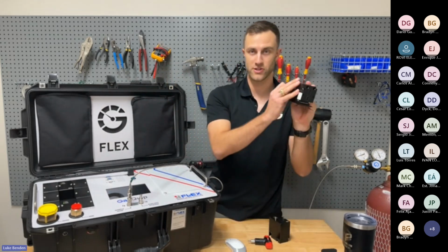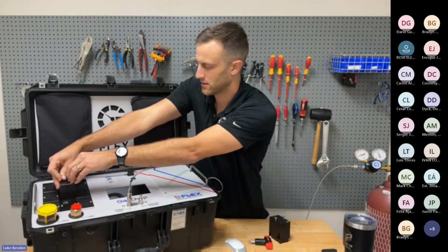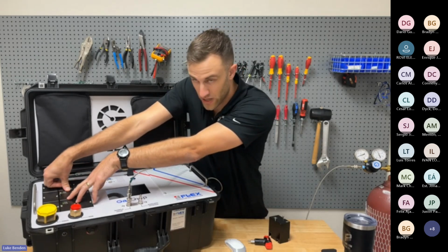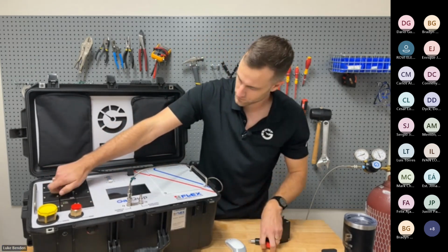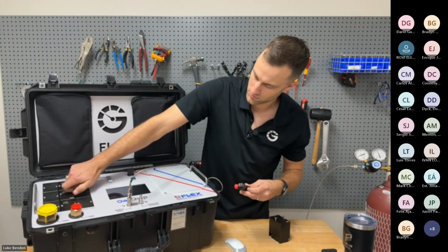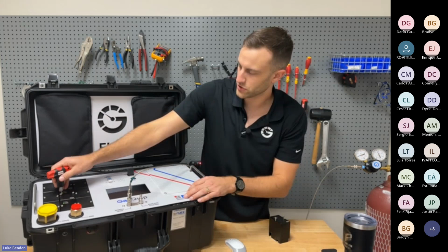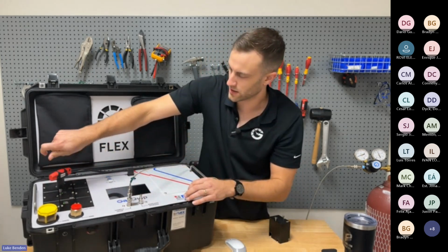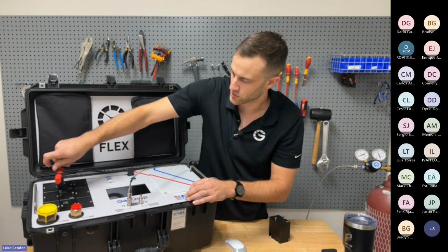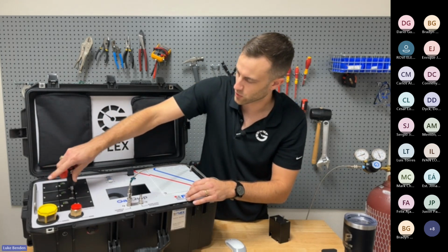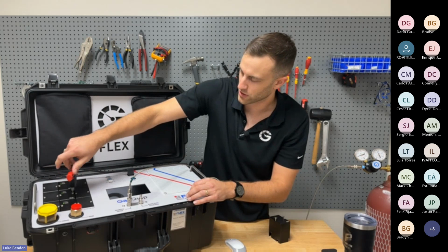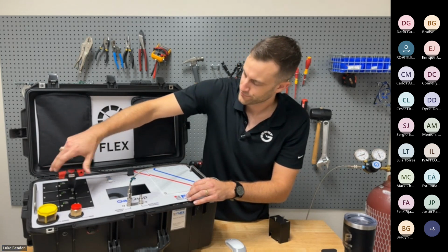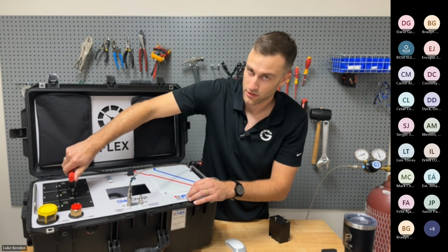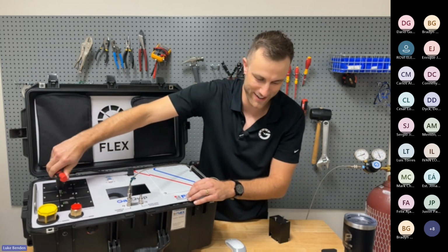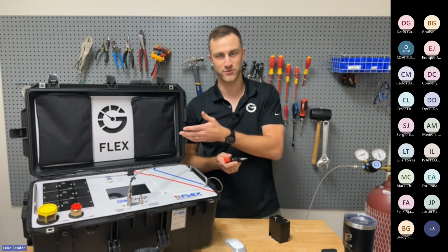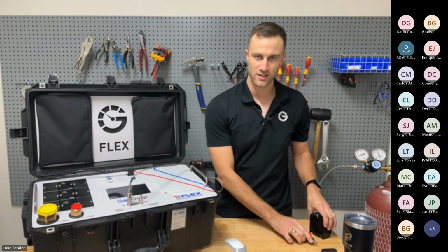You would take your new sensor module and plop that back in with the new calibration data on there. And all you do is just push that down and tighten these up. And then you take your torque wrench and tighten these down. And this is set to the predetermined torque that you need. So it'll click once you've reached the torque, and it won't let you tighten it or over tighten it once you're already bottomed out. So we got a click there and a click here like that. And that's all there is to it as far as the calibration goes for each of the sensor modules. Pretty quick and easy there.